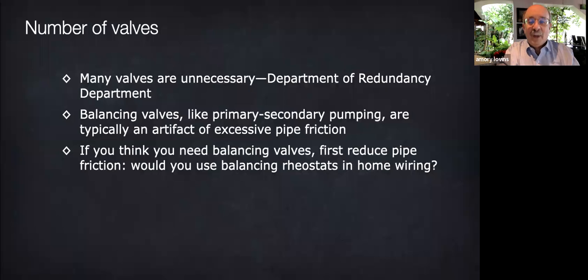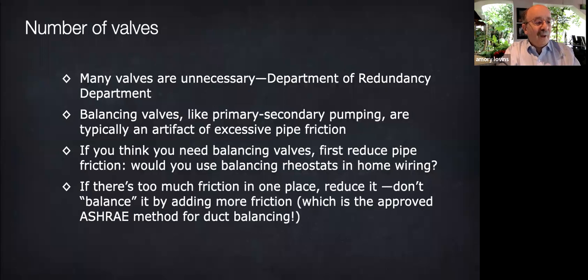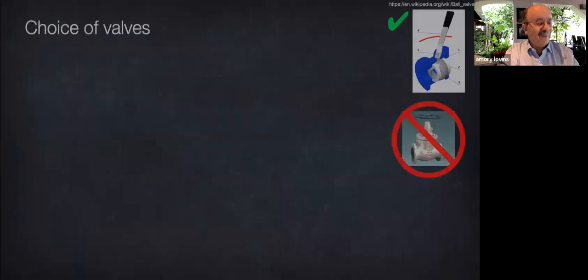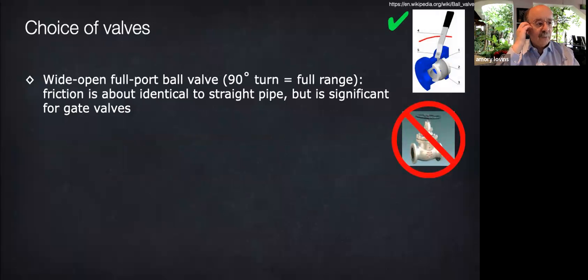You just make the wire fat enough and let Mr. Kirchhoff do the work. If there's too much friction in one place, reduce it. Whereas actually the approved ASHRAE method for duct balancing is to balance it by adding more friction in places that don't have enough. Huh? What are they thinking of? And then choice of valves matters a lot. Where you really need them, some simple choices can greatly reduce friction.